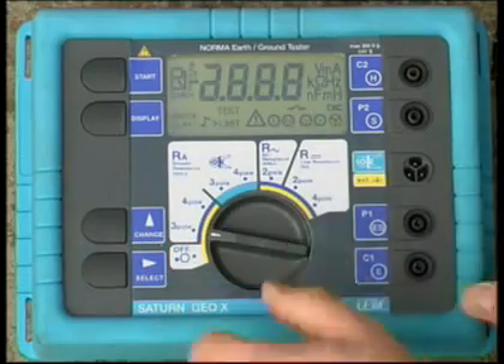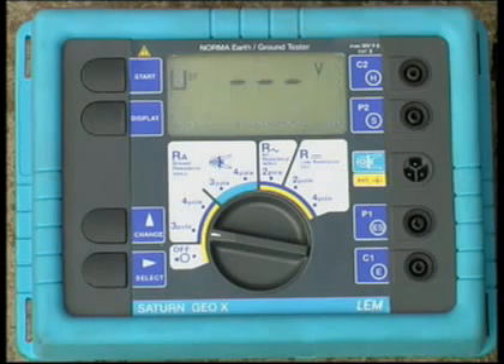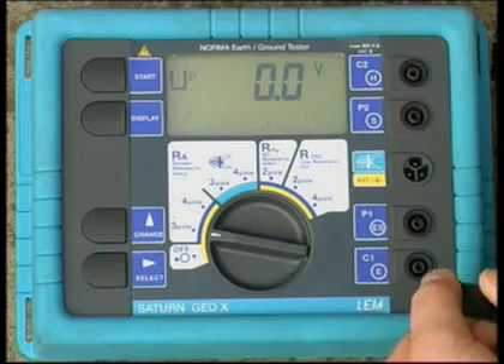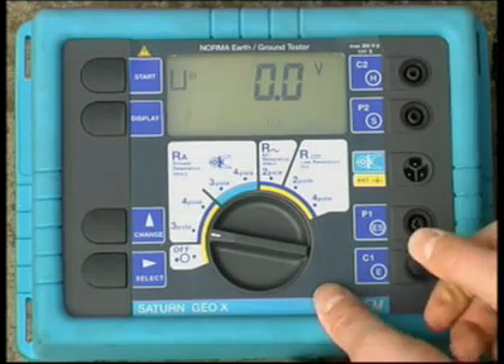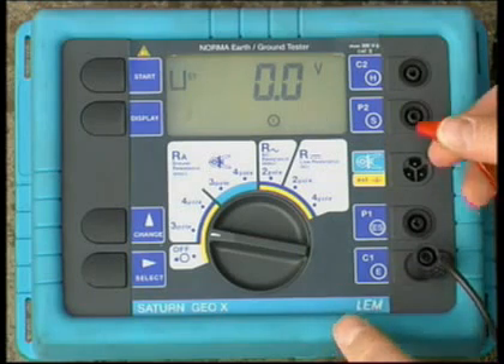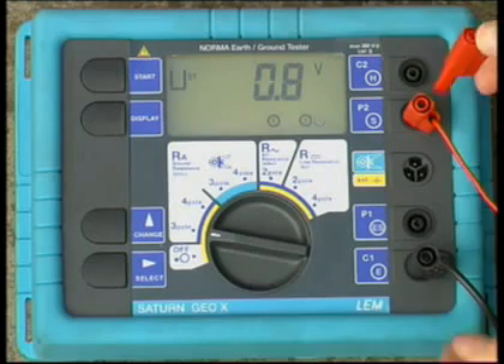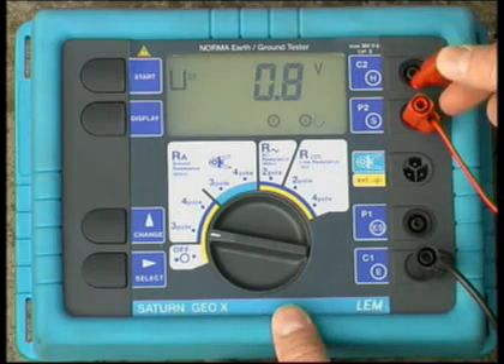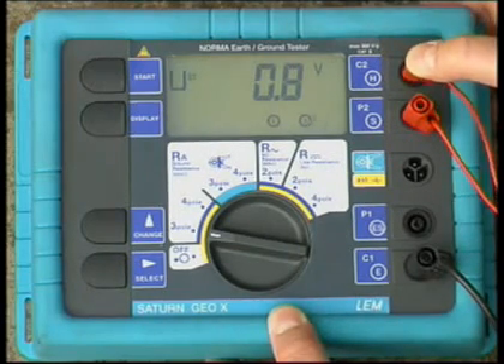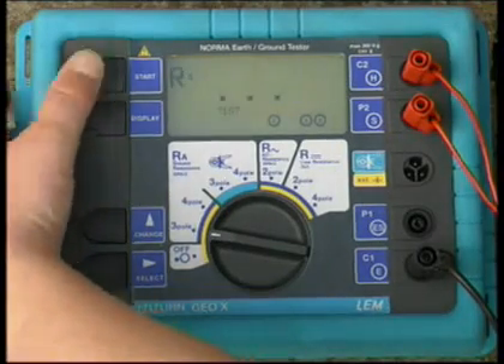Turn the central rotary switch to position Ra 3-pole. The instrument is to be wired according to the pictures and notices given on the display. The short one-meter black cable connects to the E socket, the probe electrode connects to the S socket, and the auxiliary earth electrode connects to the H socket. Press start.